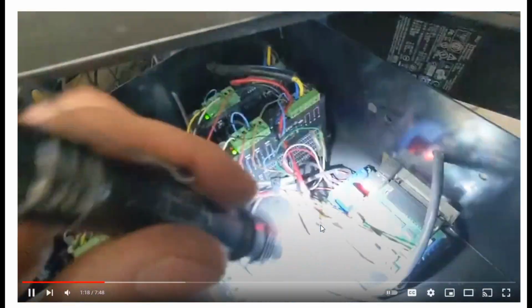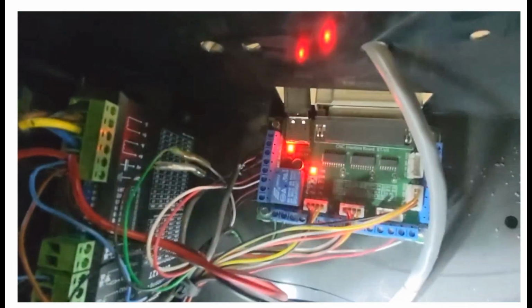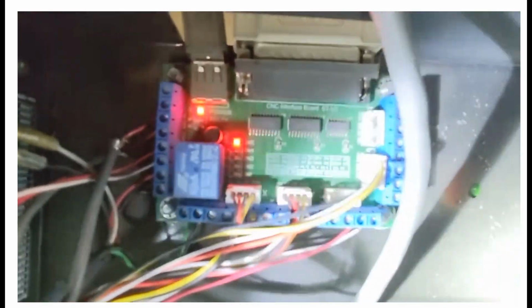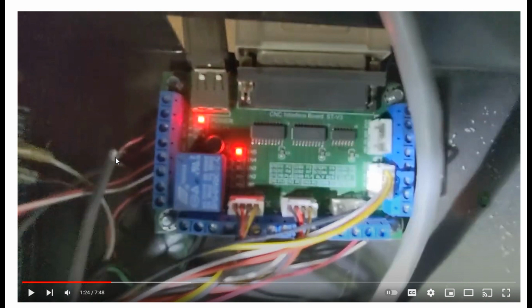Those are your step drivers. Okay, pop in here, this breakout board. Printed on these, they do have, we can see over here, the shield. And I don't know if he thinks, he must think that because I believe it's a shield, that because the cable has shielding and no drain is associated with the ground, he doesn't have to worry about EMI. Guys, if you connect cables that are shielded or double shielded for that matter, that do not have a ground drain allocated to a ground bus in the system with an actual continuity ground bus bar, you are SOL. That cable will function just as a regular cable, transferring signals, and will not perform as it should, mitigating EMI.